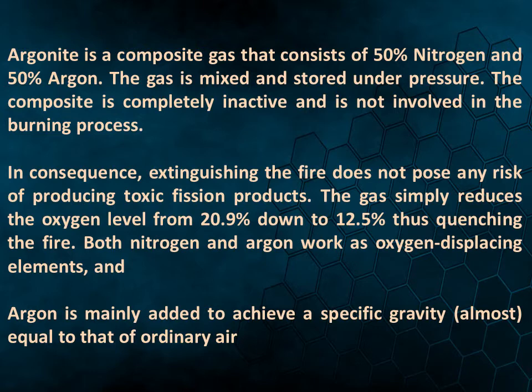In consequence, extinguishing the fire does not pose any risk of producing toxic fission products. The gas simply reduces the oxygen level from 20.9% down to 12.5%, thus quenching the fire. Both nitrogen and argon work as oxygen displacing elements. Argon is mainly added to achieve a specific gravity almost equal to that of ordinary air.